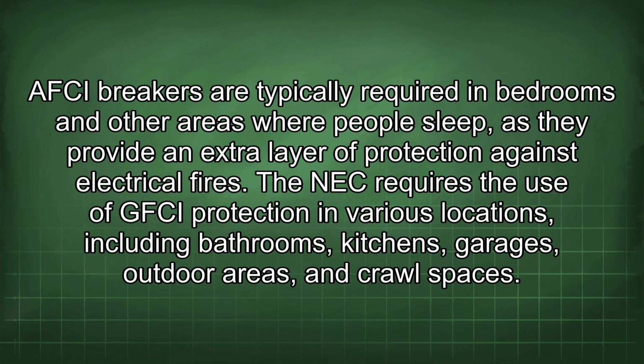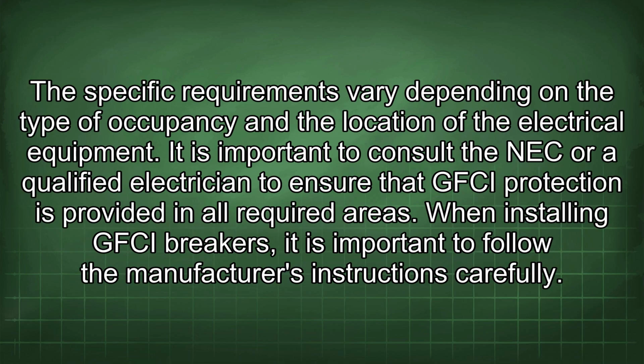AFCI breakers are typically required in bedrooms and other areas where people sleep, as they provide an extra layer of protection against electrical fires. The NEC requires the use of GFCI protection in various locations, including bathrooms, kitchens, garages, outdoor areas, and crawl spaces. The specific requirements vary depending on the type of occupancy and the location of the electrical equipment. It is important to consult the NEC or a qualified electrician to ensure that GFCI protection is provided in all required areas.